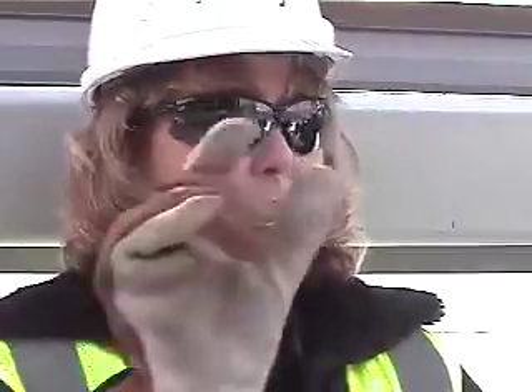Well, on this side, to me, this one's one, but standing on the other side, they might think that one's one, and I'm not sure how you guys are designating your cooling towers. And then I have one customer whose first and third cells were installed incorrectly at the VFD. So they've marked on the VFD third cell, second cell, first cell, but they're numbered the opposite way outside. So you can see where that could lead to a tragedy. So if you just lock it out here, then you don't have to worry about it.